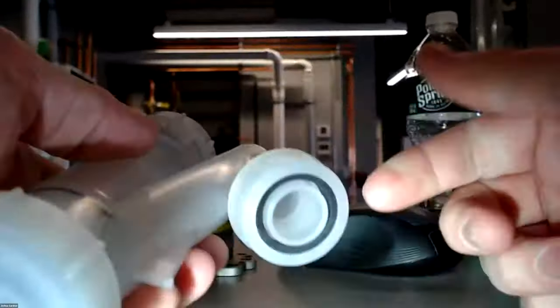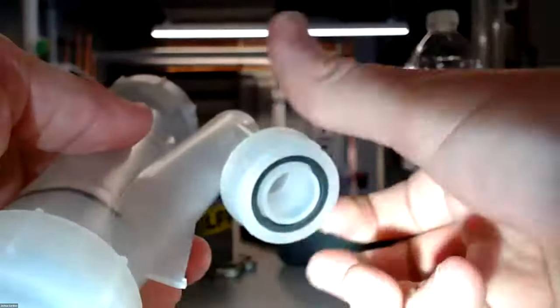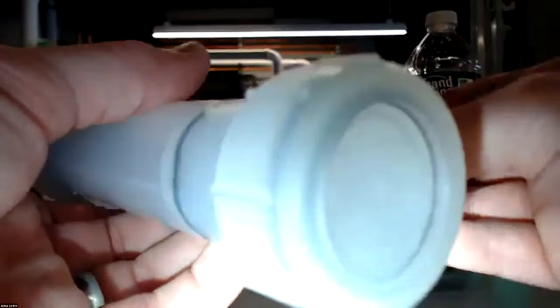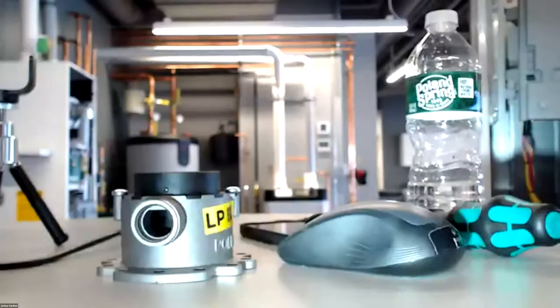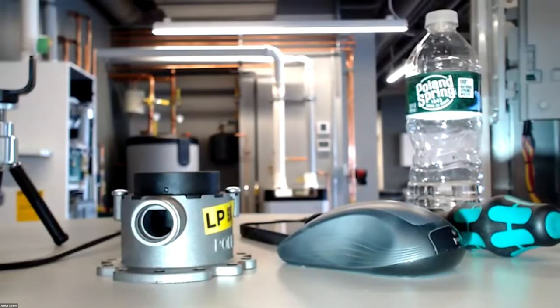Obviously the tape will be removed. Okay. And then your tubing will come out this side. Same thing. Except in this one, there's just one rubber gasket. Okay. That's one thing to note in the condensate trap that I get calls on once in a while. So that's the combi with the condensate trap.